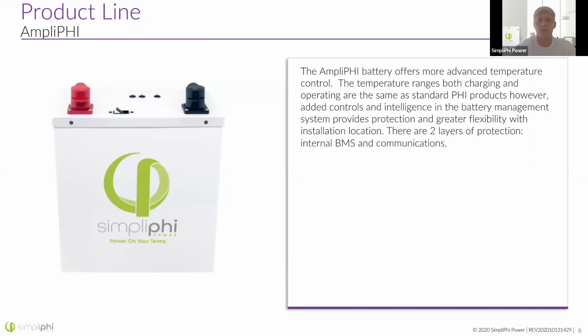The inverter charger will listen to that and ramp down the charging rate as it gets colder, even turning it off once the battery cannot accept a charge anymore. In addition to communications causing that protection in cold weather, there's also communication within the battery itself—the BMS has a fail-safe in case communications fail. But really, if you're using this battery in a cold environment, you definitely want to make sure communications are active.